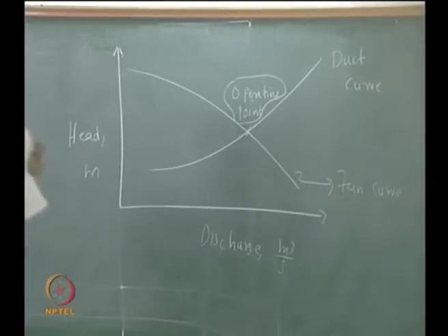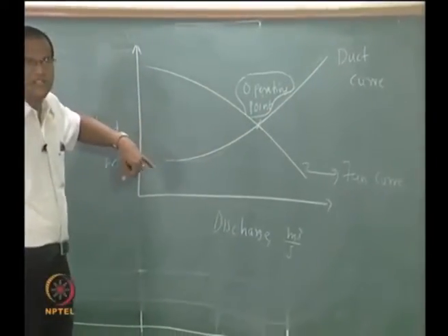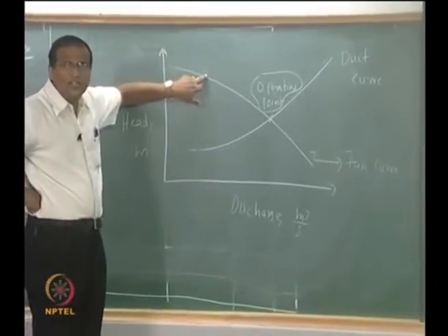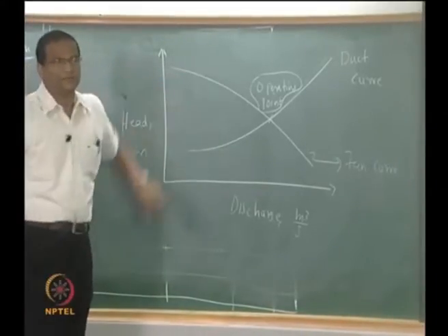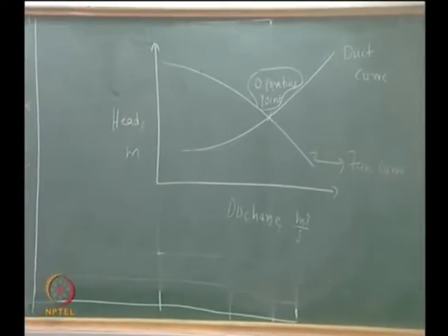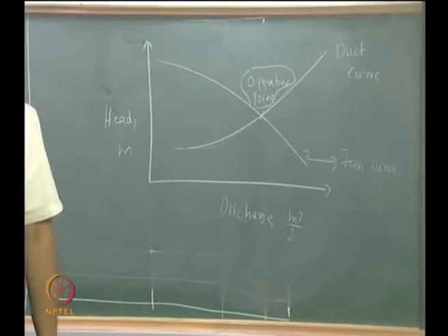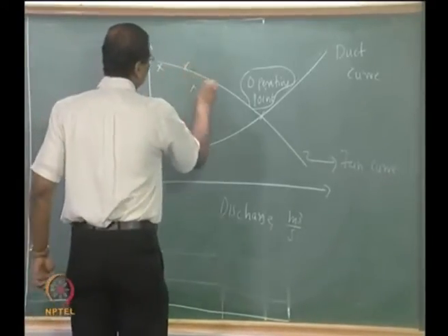So using system simulation, we want to calculate this operating point. This can be easily calculated because this is based on a formula, right? If you know the friction factor, and all this, you can calculate it. How do we get this? So this you have to get from the manufacturer's catalog or whatever. How will he have got this? So basically you have to do experiments. You will first do experiments with no discharge, zero discharge, then you will slowly increase the discharge and you will find out the head, and you will do an experiment connecting this, and so therefore you may get some points like this.